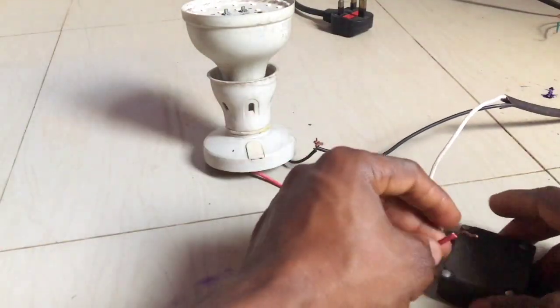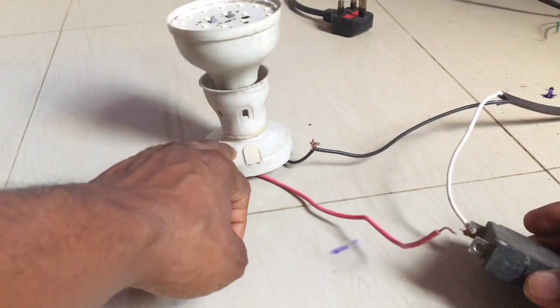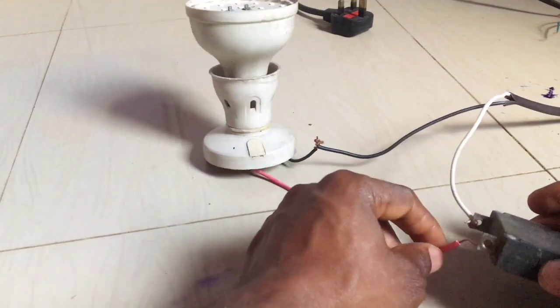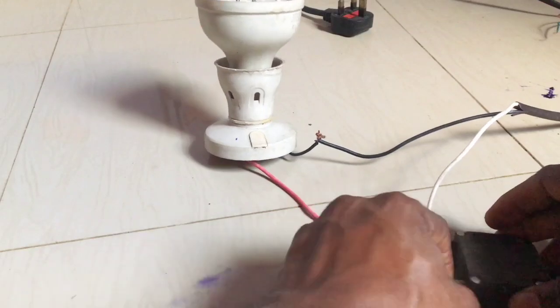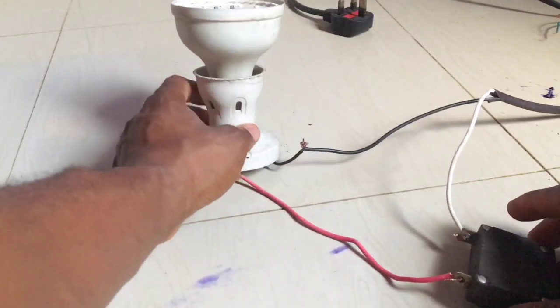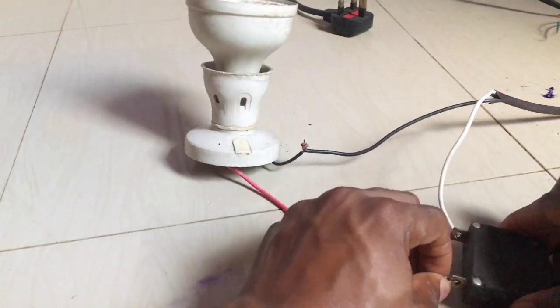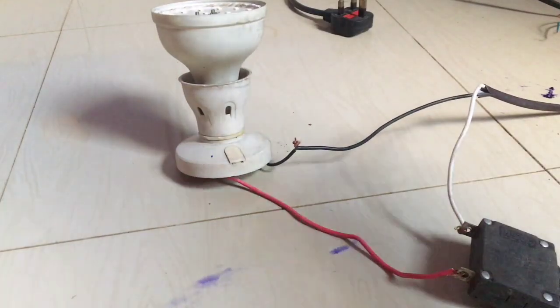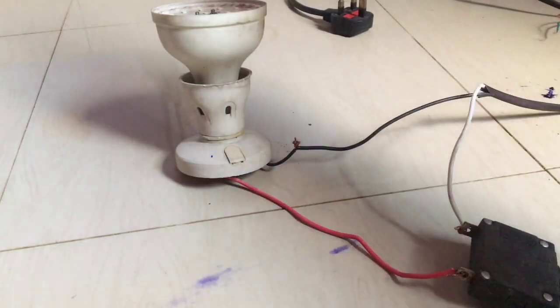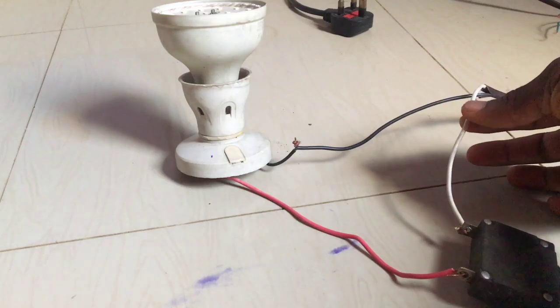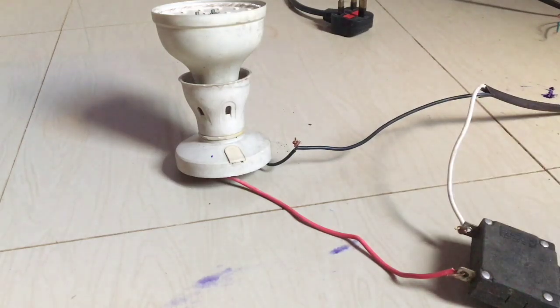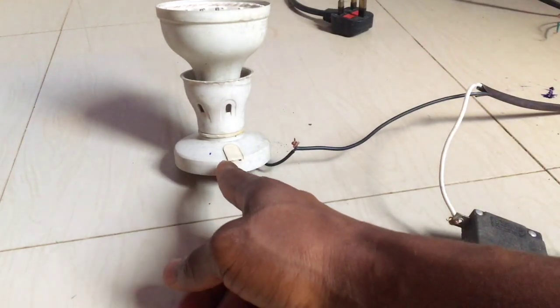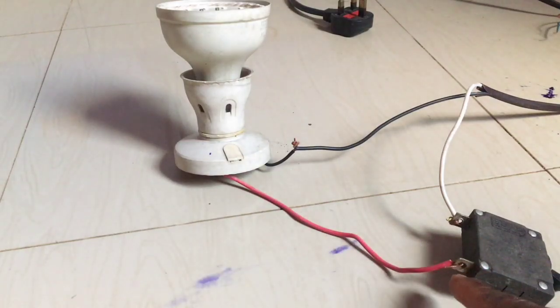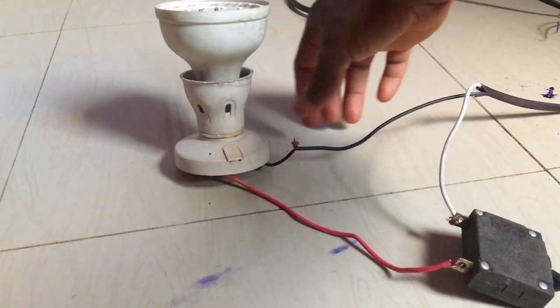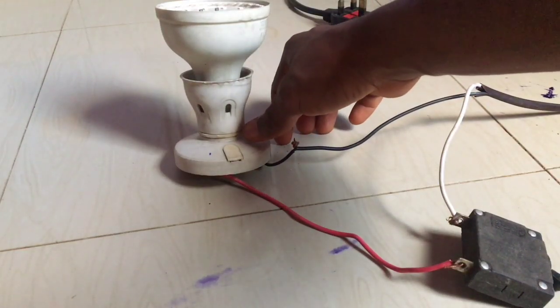The red, that's the live wire of the lighting point, goes straight to the L1 of the switch. So this is just the connection, guys. There is no joining, no junction box anywhere. Live from the distribution board comes to the common terminal of the switch. Red from the lighting point comes to the L1, the branch terminal of the switch. Then neutral from the distribution board goes straight to neutral of the lamp holder.